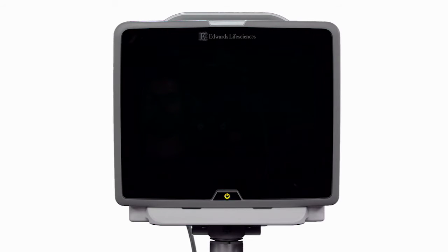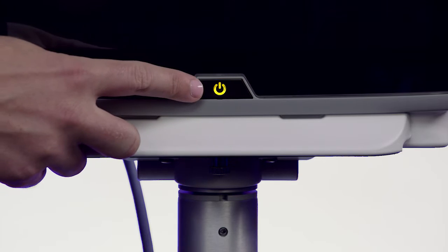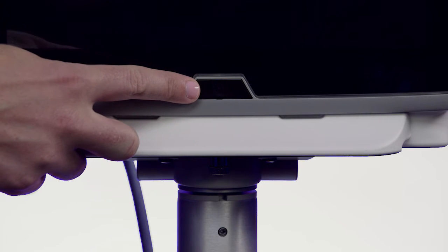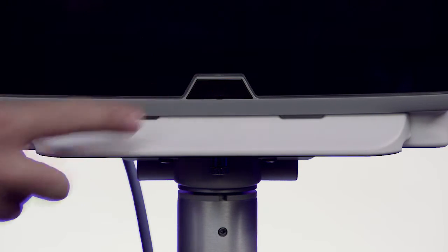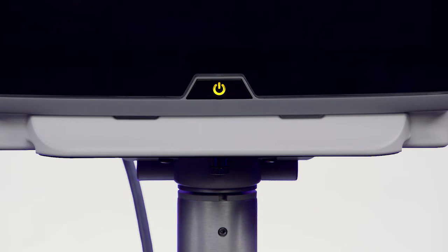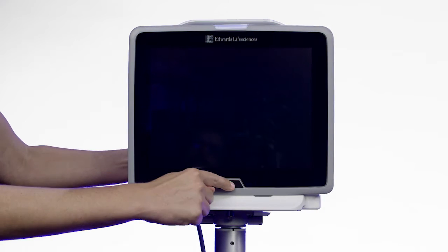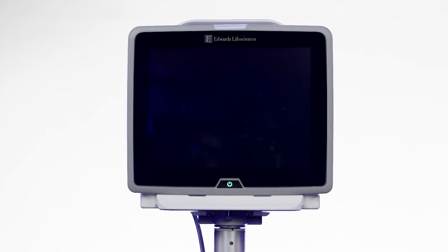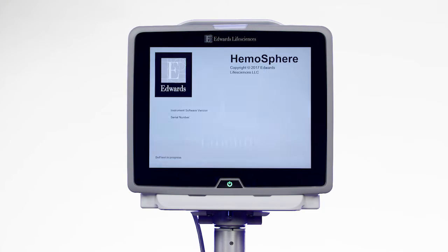The monitor power light will flash yellow when the monitor is off, when it is connected to AC power, and the battery is charging. Before unplugging from AC power, it is recommended to wait for the light to turn solid yellow, indicating the battery is fully charged. To turn the unit on, press the power button. Once the unit has been powered on, the power indicator light will turn green and the startup procedure will begin.